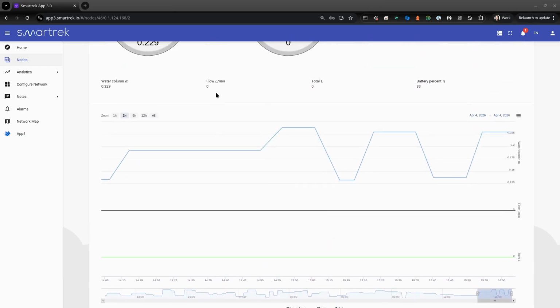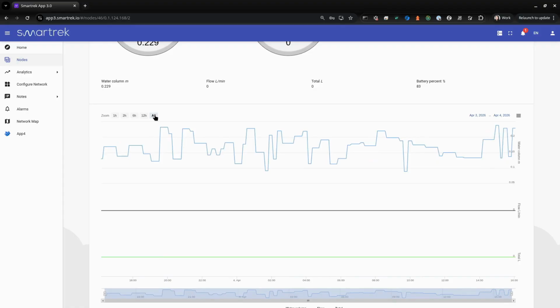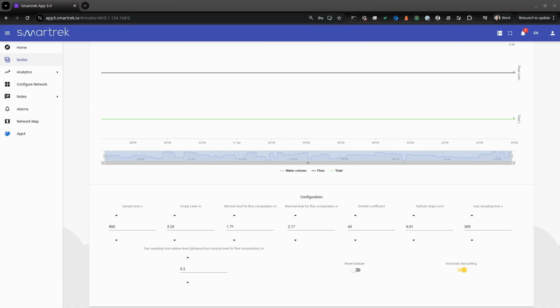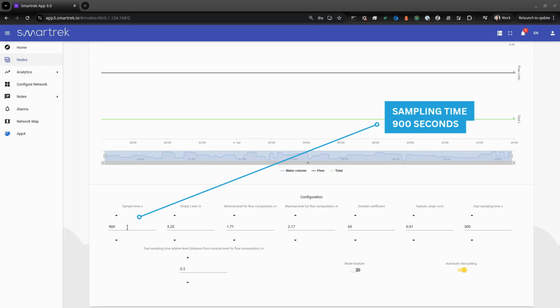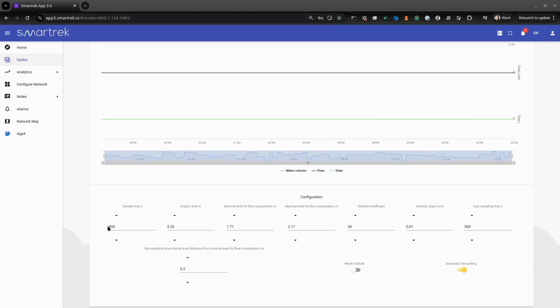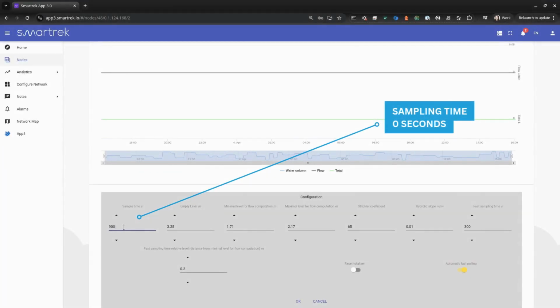Then, inspect the sensor's graph for the last 24 hours. Confirm that the sampling period is properly set to a probe reading every 900 seconds, or 15 minutes. If you'd like to run an overflow simulation, or if you want to make changes to the sensor's settings, set the sampling period to 0 to get new readings more quickly.